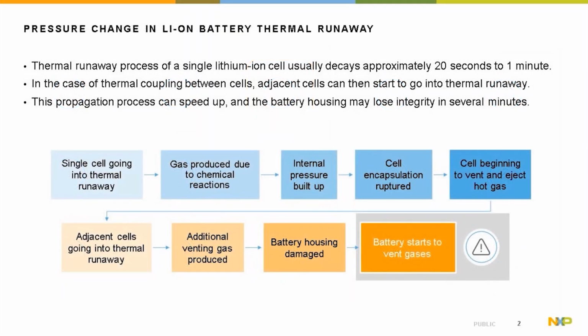Let's look at pressure change in lithium-ion battery thermal runaway. As one cell goes into thermal runaway, gases are produced due to a chemical reaction, which causes the internal pressure to build up and the cell encapsulation to rupture. The cell then begins to vent and eject hot gases.